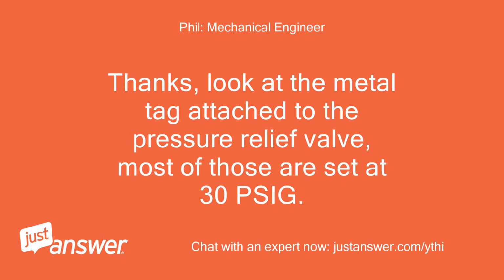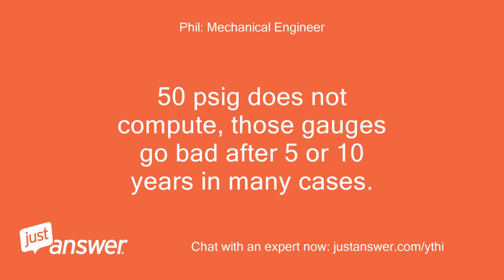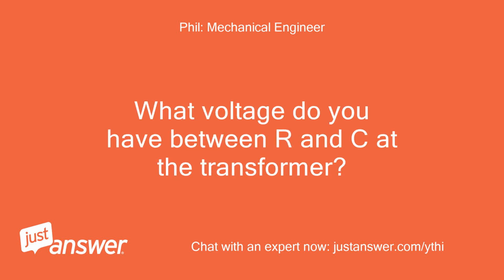Thanks. Look at the metal tag attached to the pressure relief valve. Most of those are set at 30 psig. 50 psig does not compute. Those gauges go bad after 5 or 10 years in many cases. What voltage do you have between R and C at the transformer?